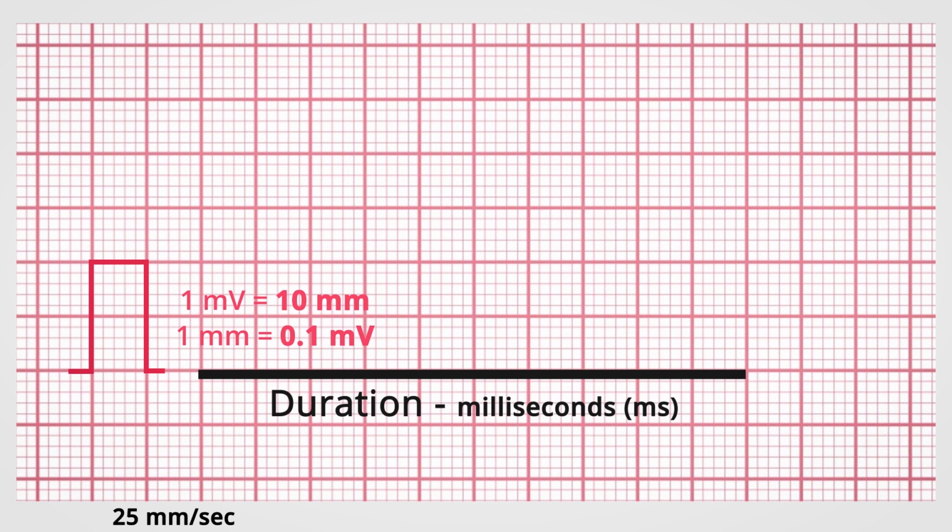At the beginning of each ECG wave, voltage is indicated by this bar. A bar covering 2 large squares indicates that the ECG has been recorded at standard voltage. This is important to see because sometimes the ECG may be erroneously recorded at low or high voltage, resulting in low or high voltage ECG waves, which can be wrongly attributed to pathology, and that would subject a person to unnecessary investigations.